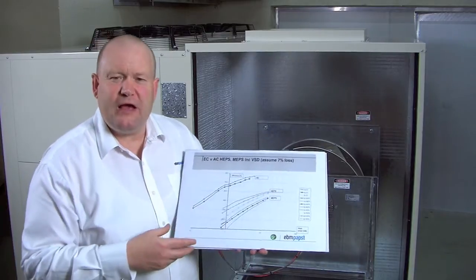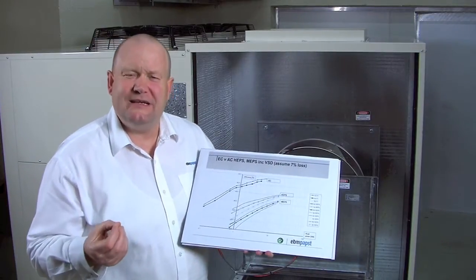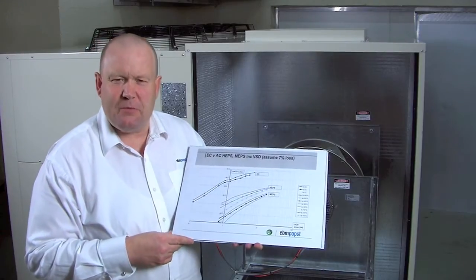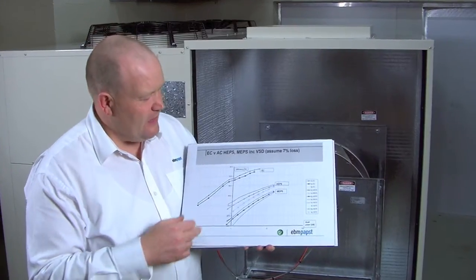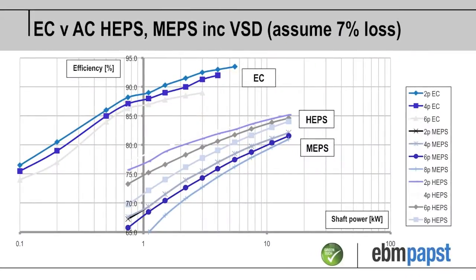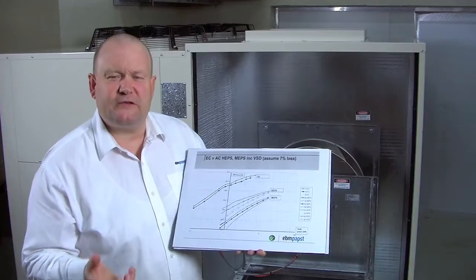In this slide I've compared the difference between EC motors and AC motors under speed control according to the minimum energy performance standards. And here you can see that I've put a VSD calculation on the AC motors and the MEPS standard and I've assumed 7 percent losses inside the VSD such that we've got an apples for apples comparison between EC.